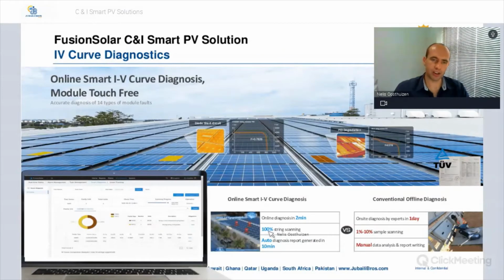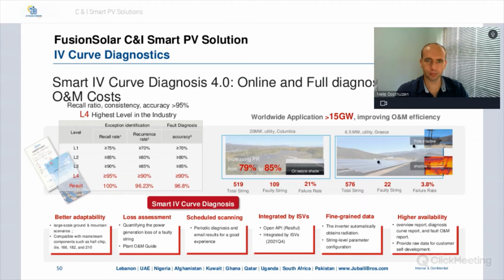With the Huawei system, you're guaranteed 100% string scanning, but if somebody's out on site, it's only maybe 1 to 10% sample scanning, as they will just scan where they think a problem might be. And with the conventional method, you also have manual data analysis and report writing, whereas on Huawei it's an auto-generated report. Smart IV curve diagnostics 4.0 is online and full diagnosis, reducing your O&M cost. The recall ratio and consistency accuracy is more than 95%.